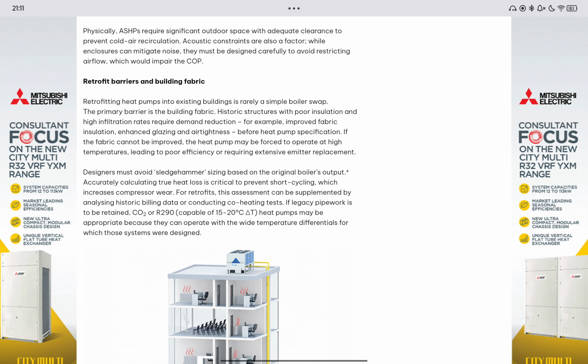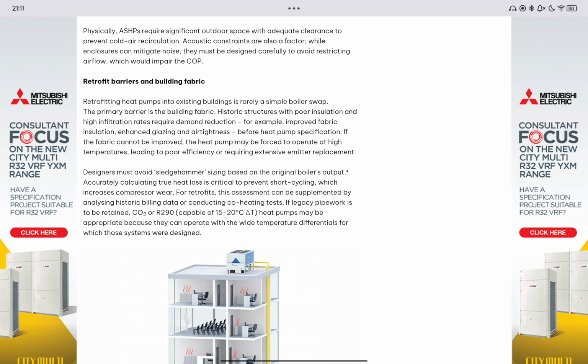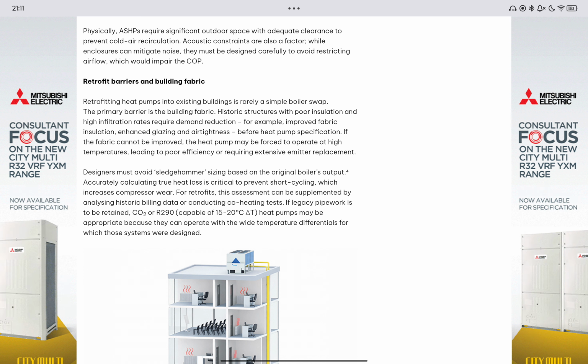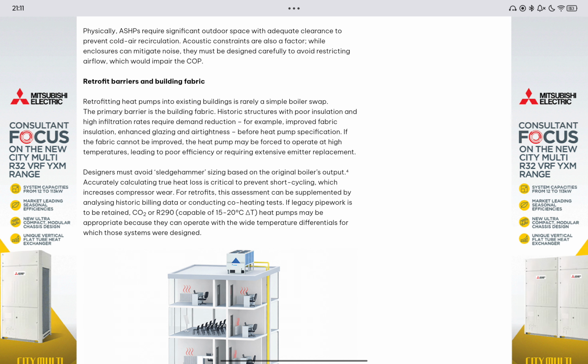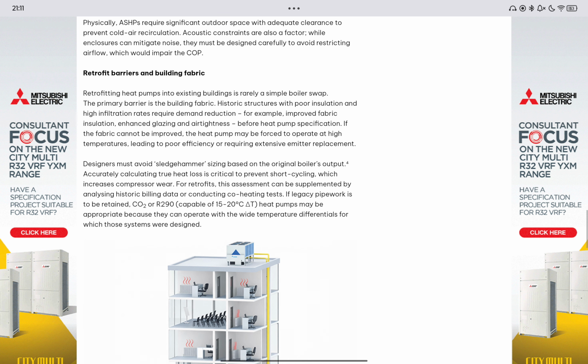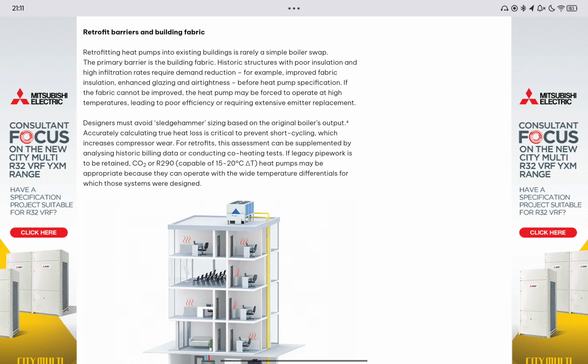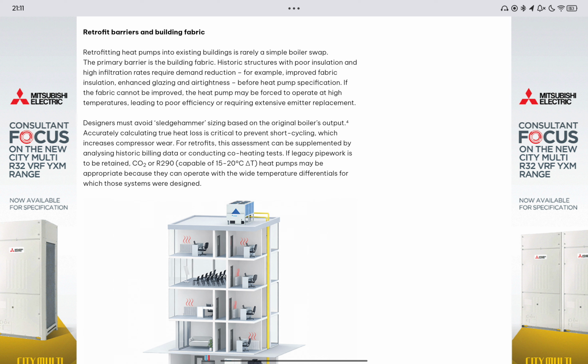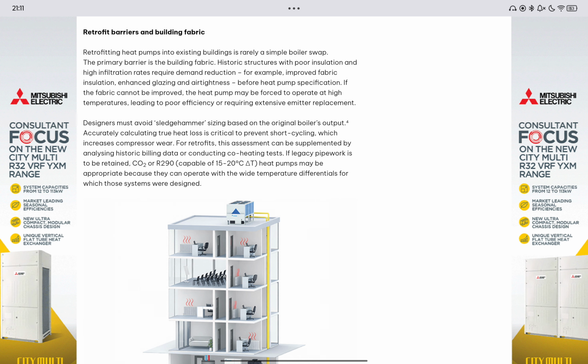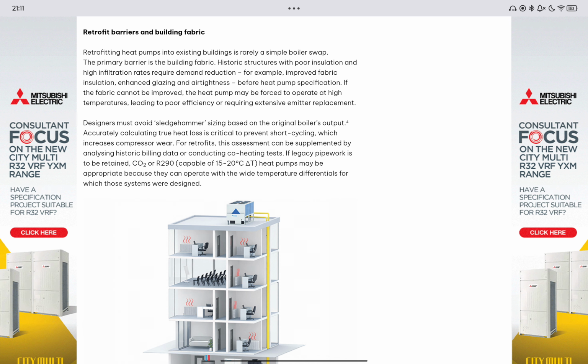Retrofitting heat pumps into existing buildings is rarely a simple boiler swap. The primary barrier is the building fabric. Historic structures with poor insulation and high infiltration rates require demand reduction, for example, improved fabric insulation, enhanced glazing and air tightness before heat pump specification. If the fabric cannot be improved, the heat pump may be forced to operate at high temperatures, leading to poor efficiency or requiring extensive emitter replacement.